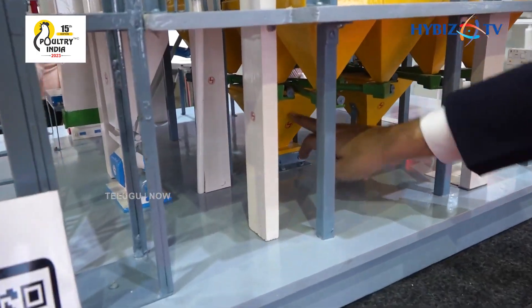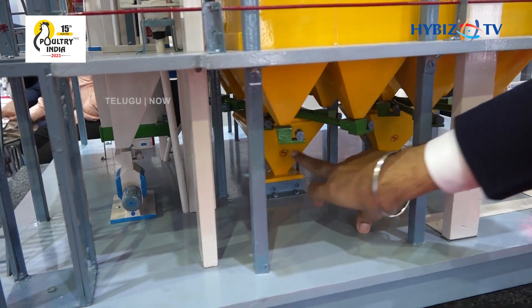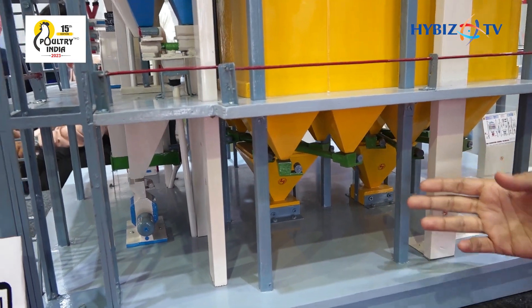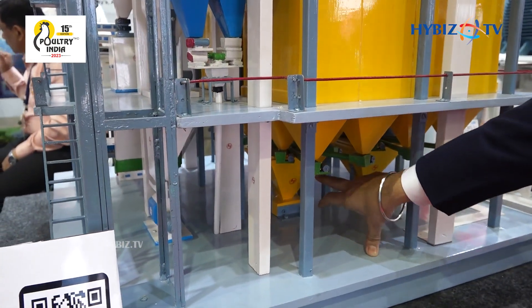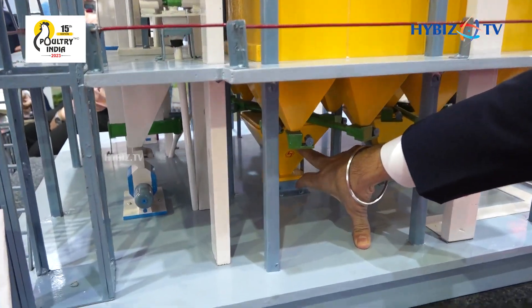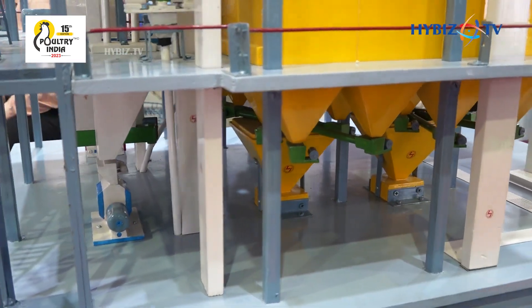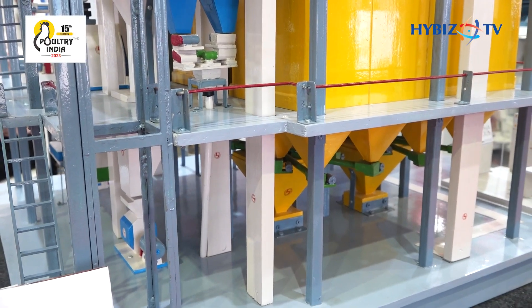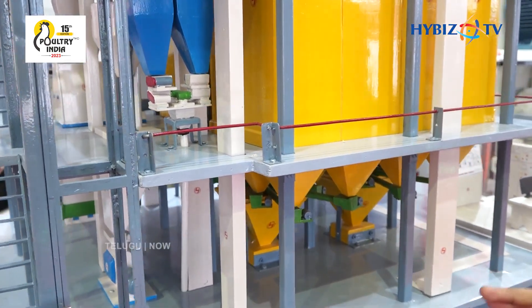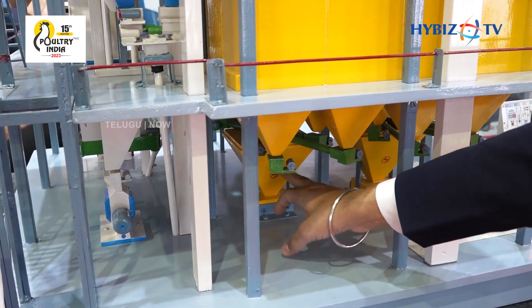Below this batching bin are the two weigh hoppers. The PLC operator just has to select the recipe and the number of batches. As per the selection and number of batches, all the batches come to these weigh hoppers. These weigh hoppers are based on load cells. We can get perfect batching and weighing with 0.2 to 0.3 percent accuracy, depending upon the weight, the dose, and the ingredient behavior.